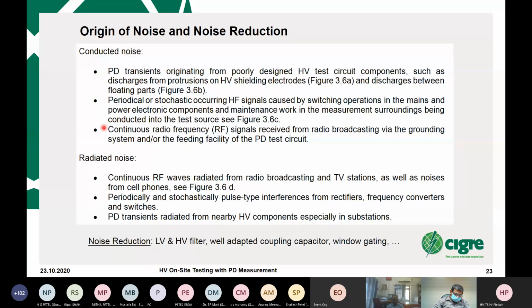Is there radio frequency disturbance nearby, like a radio or TV station - for example, if bushings are connected to the transformer or to the GIS, that's a typical source. Or if you have an air-insulated substation close to a GIS substation under rainy conditions, you could get very high noise.